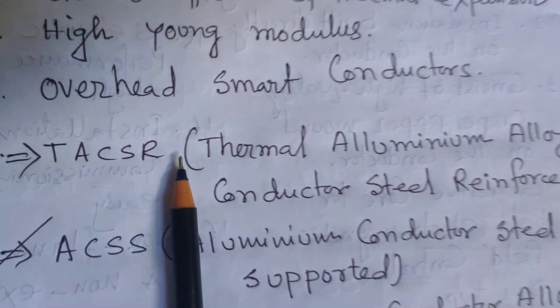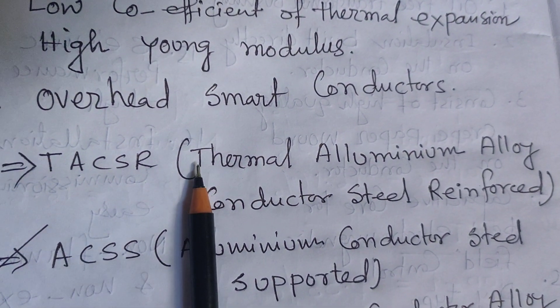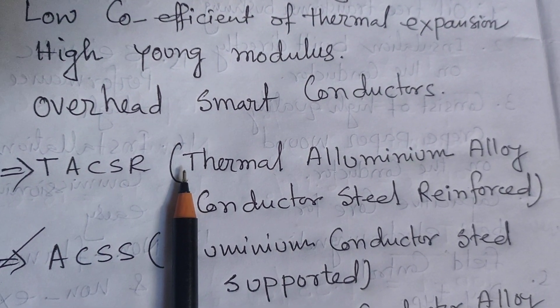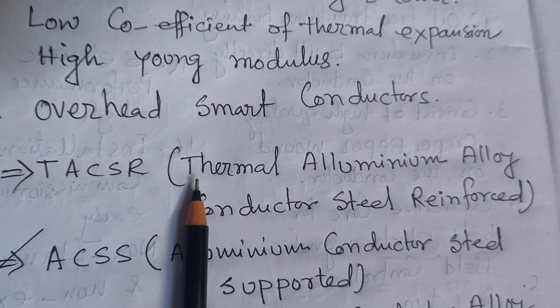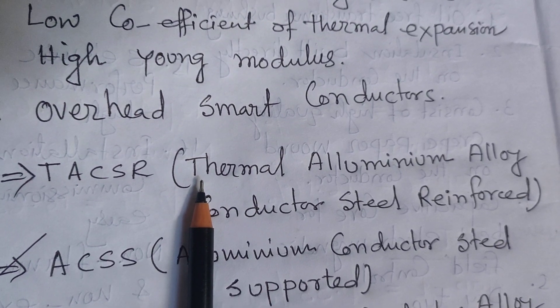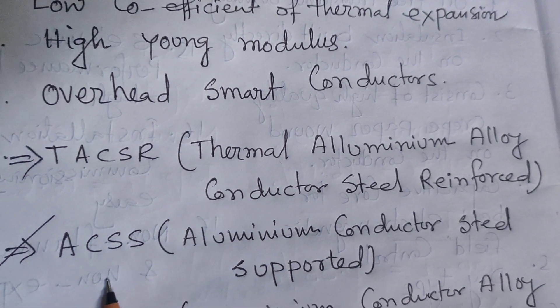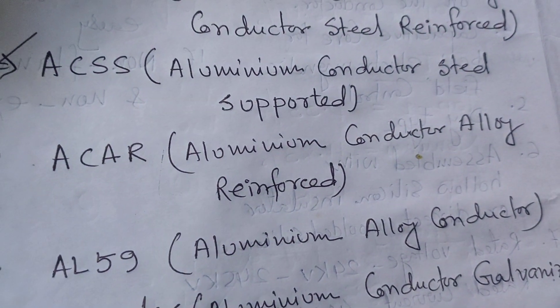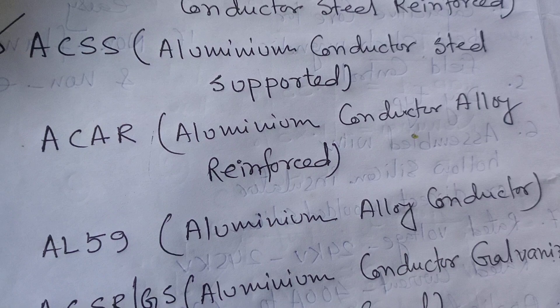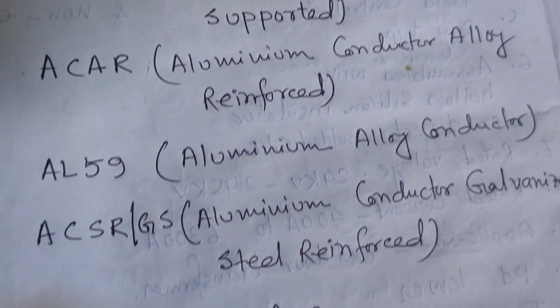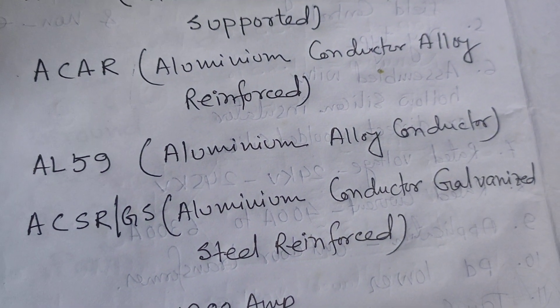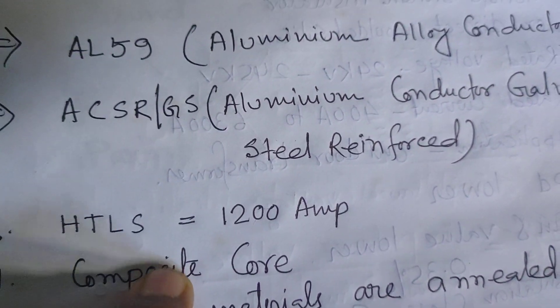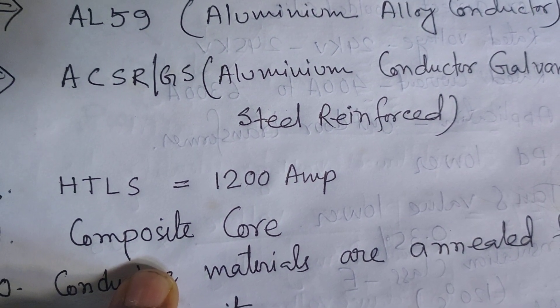Few types of HTLS conductors are now being used in India and throughout the world for the betterment of society, to flow lots of current while sustaining high temperatures. HTLS conductors equivalent to ACSR Zebra have capacity to flow 1200 ampere current, and equivalent to ACSR Panther have 800 ampere capacity.